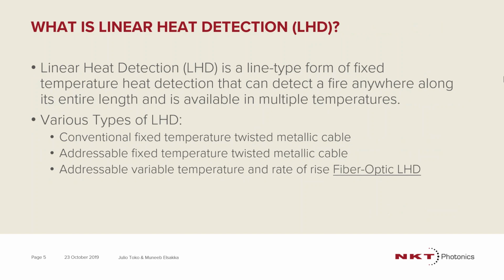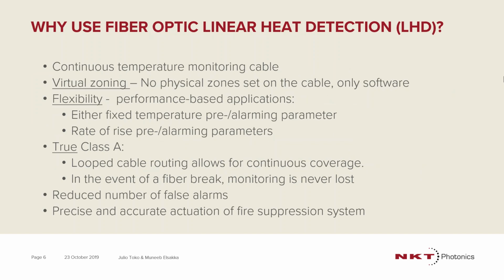So what is linear heat detection? Linear heat detection is a line type form of fixed temperature detection that can detect fire along its entire length and is available in multiple temperatures. You have various types of LHD systems. You have the conventional fixed temperature twisted metallic cable, as well as the addressable version of this. You also have an addressable variable temperature and rate of rise fiber optic linear heat detection system, which we'll be discussing in detail today with you.